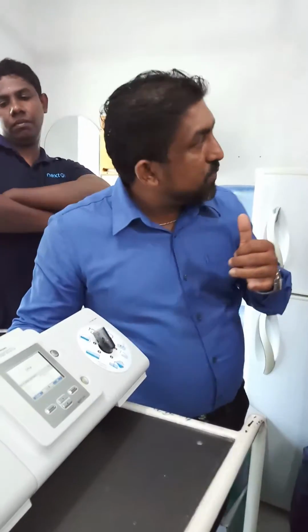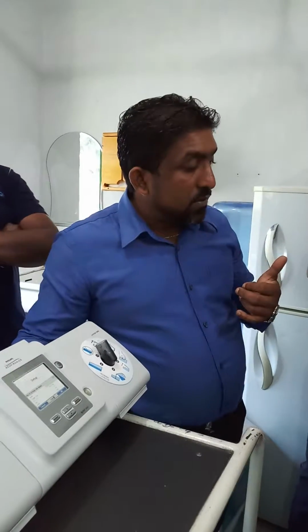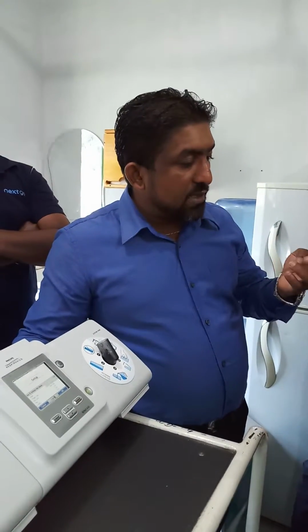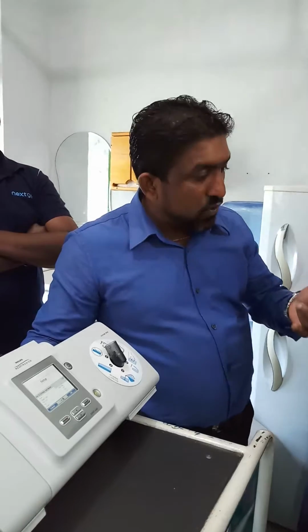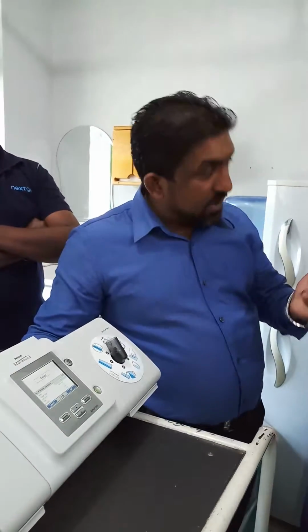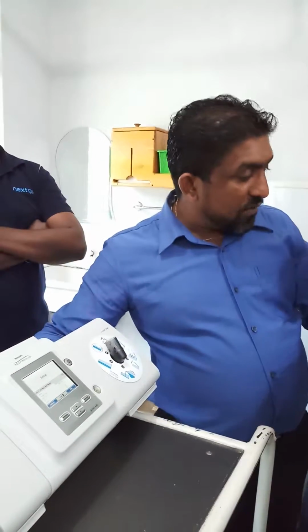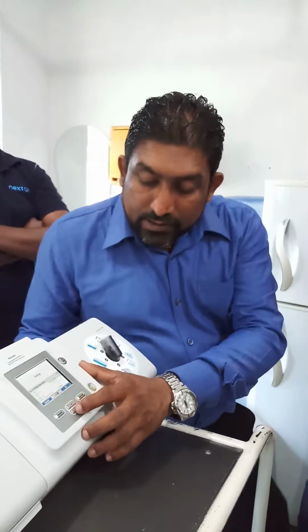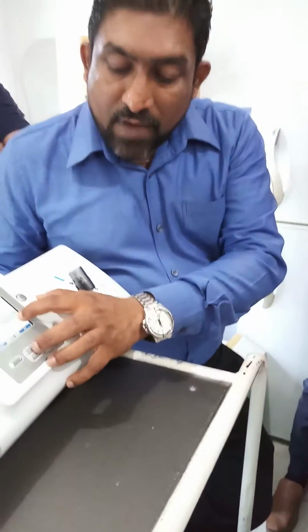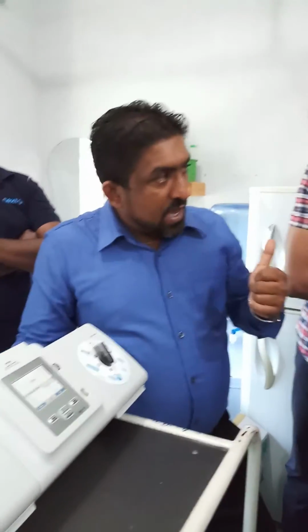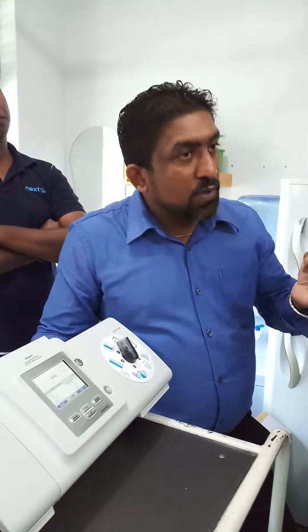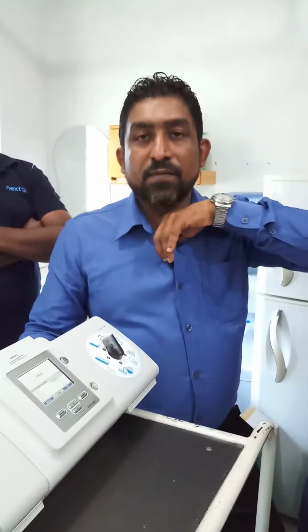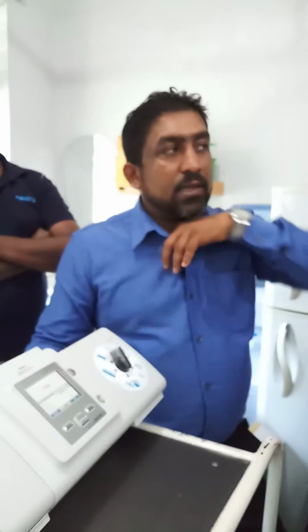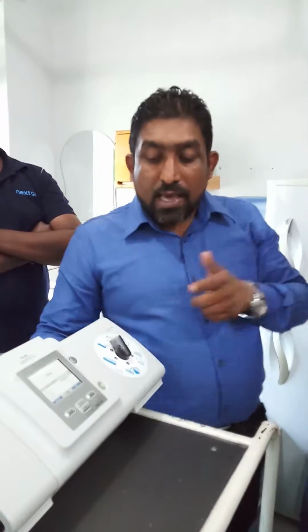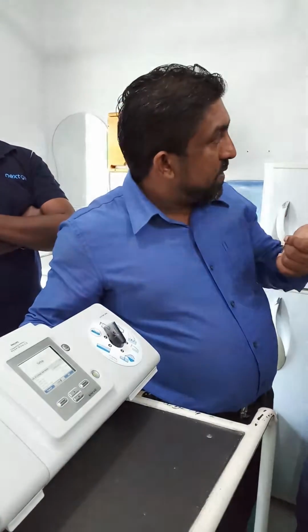S mode means spontaneous mode. So how many modes? S, ST, S mode, spontaneous mode. AVAPS A, you have to write down. AVAPS A means average volume assured pressure support. That is a special mode which Philips gives for this machine. That is AVAPS A. A means auto EPAP.